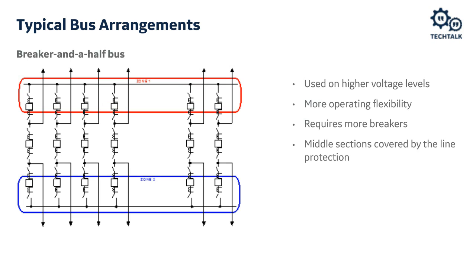The breaker-and-a-half bus is one of the most reliable designs in terms of bus topology, used at higher voltage levels, offering maximum operating flexibility. However, the drawback is it requires more breakers, which requires more real estate, making it a costly arrangement. In this scheme we have two buses, and loads and sources are always connected to both through the breaker-and-a-half on each section. The loads and sources on each section are protected by their own protection systems, while the bus zone itself is protected by its own bus zone protection.